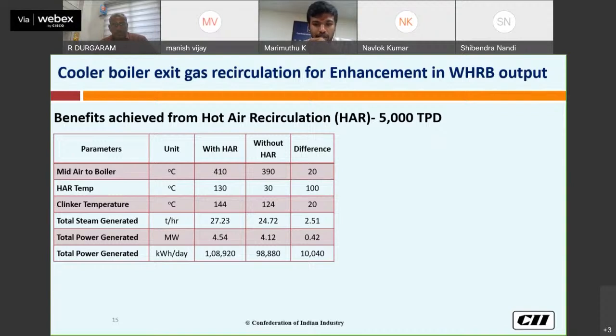These are all the benefits achieved from the hot air recirculation for the unit of 5,000 TPD. In this figure, we can see that without hot air circulation, the mid-air to the boiler is around 390, and with hot air circulation it increased by around 20 degrees. The hot air temperature, instead of ambient 30, is around 130 degrees centigrade. Increasing the air temperature also increases the clinker temperature, by around 20 degrees. And the steam generation, which was 24.7 in the existing case, reached 27.23 with hot air circulation, an increase of around 2.5 tons. Power generation also increased by around 0.42 megawatt.